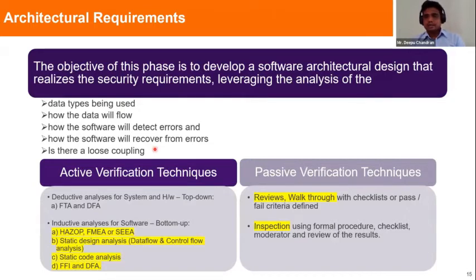Software safety analysis can be based on inductive analysis, such as Hazard and Operability study (HAZOP), FMEA, software error effect analysis, or software error effect and criticality analysis. There are many safety analysis techniques to identify errors from a bottom-up approach, because we point to the software fault and then go back to the system to see whether a software failure can really fail the complete system.